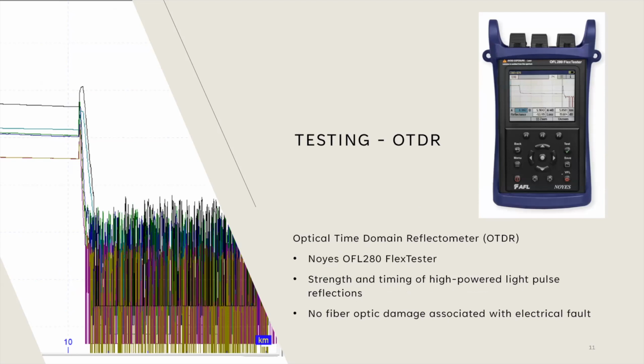Next, we tried an OTDR, a similar idea. It's an optical time domain reflectometer. Instead of a voltage pulse, it's sending a high powered light pulse down the fiber optic. Again, the timing and strength of the light returned informs where your breakage is. We were hoping that whatever damage had caused the fault that we were seeing would have been represented, and maybe it also damaged the fiber optics. We'd see it there. This is actually a trace from that cable, and you'll see the reflection came right around 10,000 meters, which was about the length of the cable.